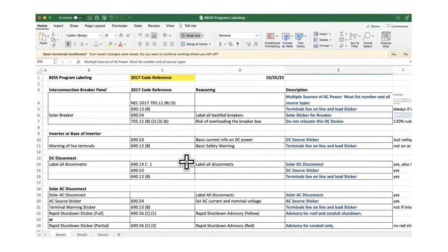Is it perhaps a utility requirement that you have? We have a utility requirement for an AC disconnect outside. Yep. And because of the way that the utility company has required us to interconnect these systems now, there winds up being two AC disconnects outside. One AC disconnect goes from the solar and shuts off the solar, and the other AC disconnect shuts off the AC from the backup. Okay. Yeah, from the energy storage system.